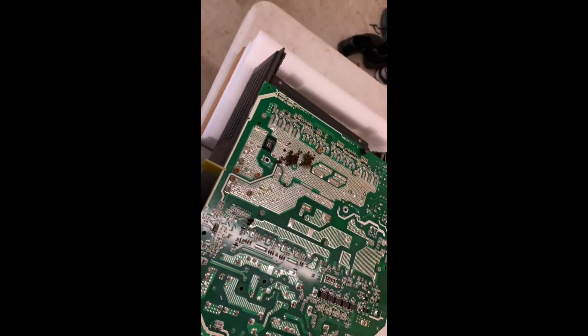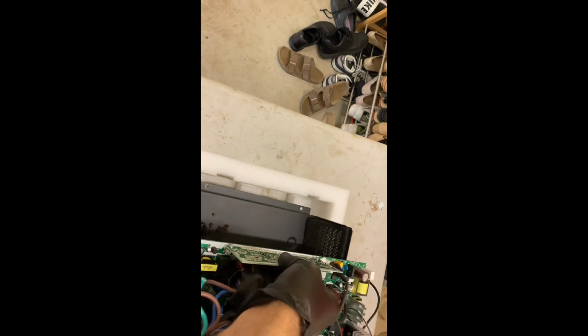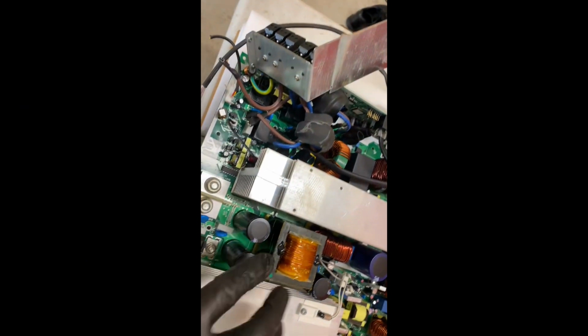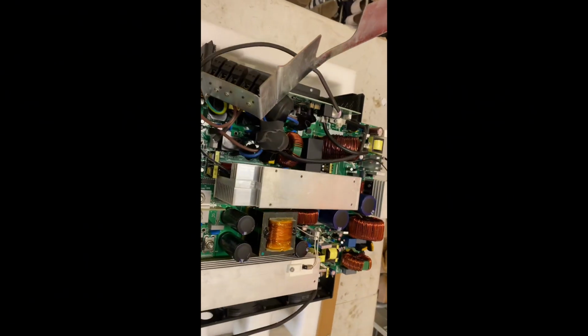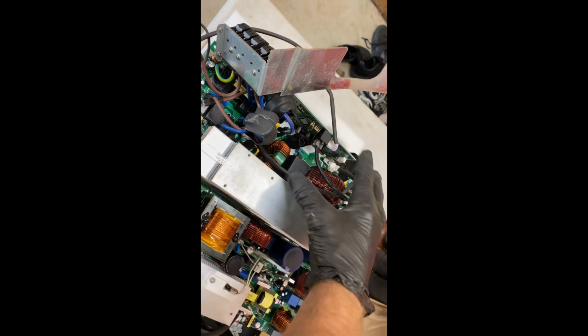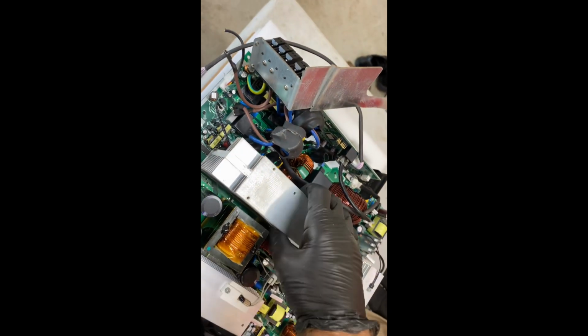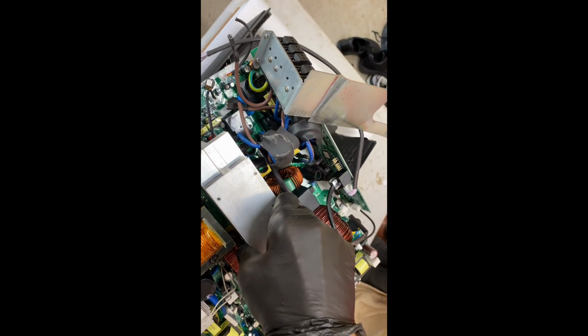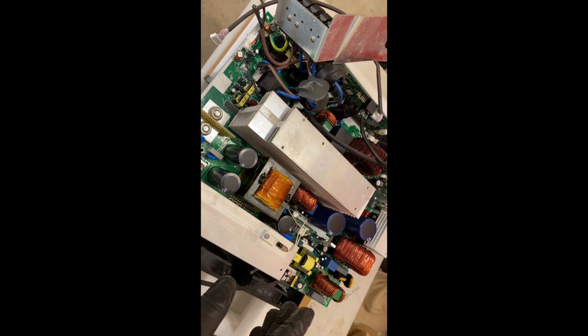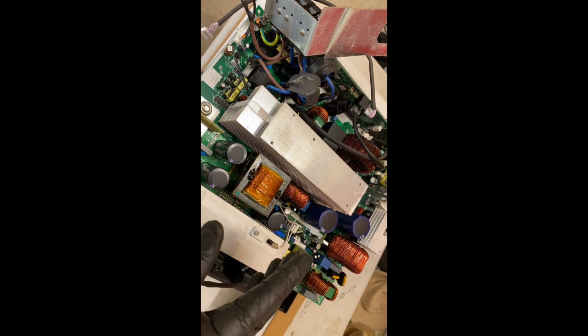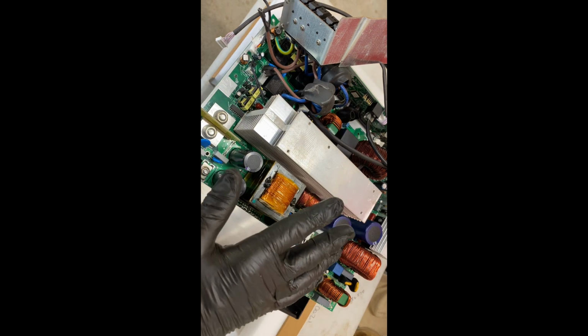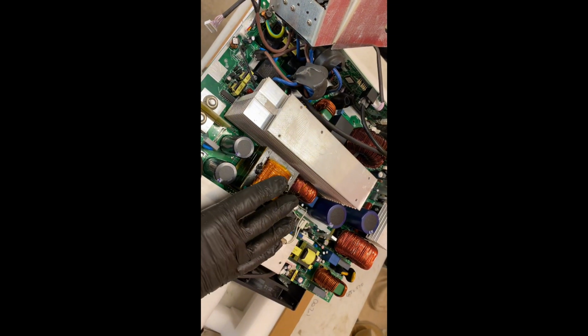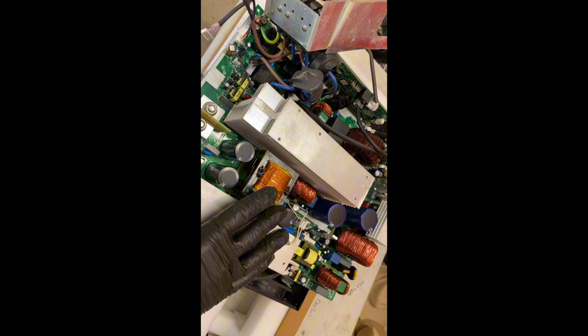Now, this is a transformerless inverter. There's a few little transformers here and there, but a Victron, Selectronic, or SMA off-grid inverter will have a big wire-wound copper transformer, and there's no way I'd be able to pick up a 5 kVA off-grid inverter with one hand like that. So if you're selecting off-grid inverters, the weight of the inverter is a very good indication of its quality, because transformerless inverters can't handle the temperatures and surge capacities like a transformer inverter can. So use that as a guide.